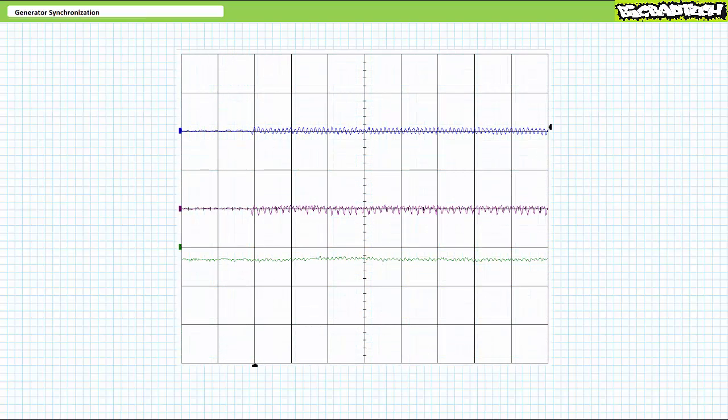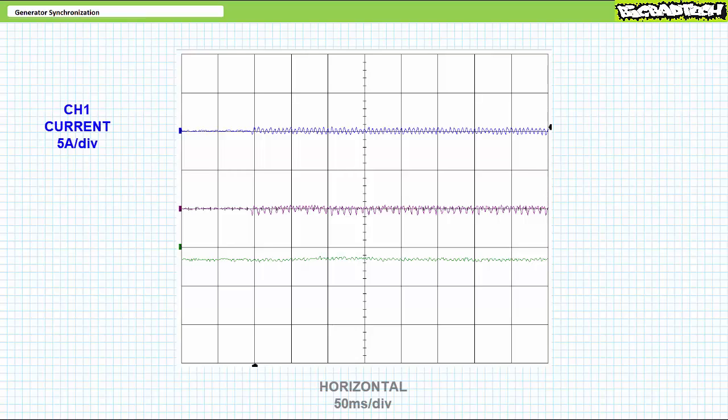Our interest is in capturing the electrical and mechanical transients, i.e. temporary events that occur during synchronization. In this scenario, we set up the generator to produce light industrial 60 Hz three-phase AC with 120 volts line to neutral and 208 volts line to line. Consider an oscilloscope trace for line current for one phase through the contactor, generator electrical power for one phase, and generator torque.